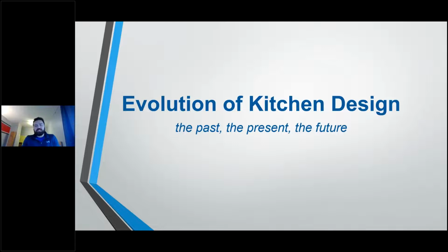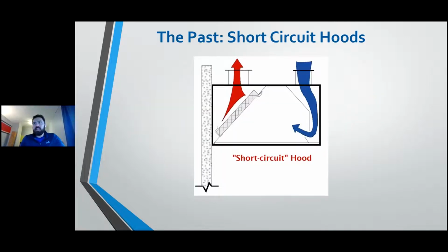All right, so the evolution of the kitchen design, and this is where I'm going to buzz through these first couple of slides and then we're going to talk about makeup air in a little bit more detail. In the 70s, the 80s, the 90s, we had what were called short circuit hoods. Because that makeup air is so expensive to temper, they would utilize short circuit hoods, and they would bring untempered makeup air into the exhaust cavity of the hood, typically 90% of total exhausted air. The idea being that the air would be introduced right into the hood so it could be balanced and it would be exhausted right away. So we don't need to pay to temper it.